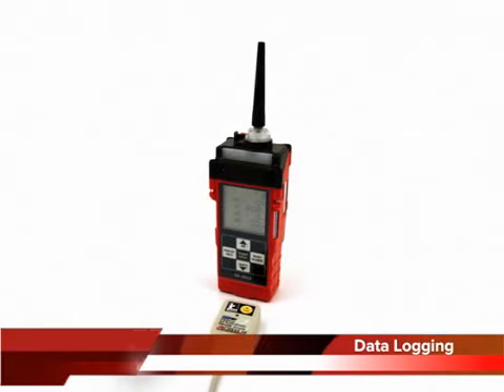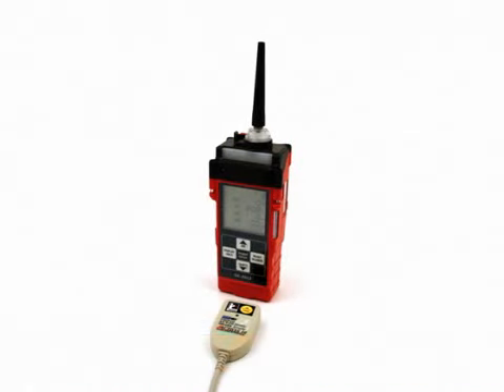The GX-2012 features the ability to log data to its internal memory and download it to a computer via the infrared communications port located just below the Reset Silence button. It logs gas readings during normal operation, alarm data, and calibration data. To utilize the GX-2012's downloading capability, you will need the GX-2012 downloading software and a computer with an infrared port or a USB port that runs one of the following operating systems: Windows XP, Windows Vista, or Windows 7.